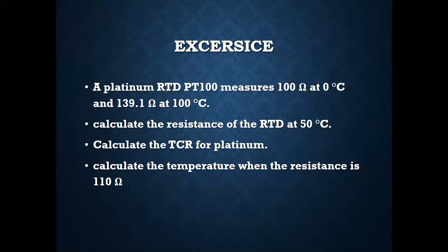You don't have to say the answer. Please try to do. What is the equation? RT, here T is equal to 50 degrees. R50 is equal to R0 into 1 plus alpha T. What is R0? 100. What is alpha? 0.00391, into T equal to 50. So I will show you.